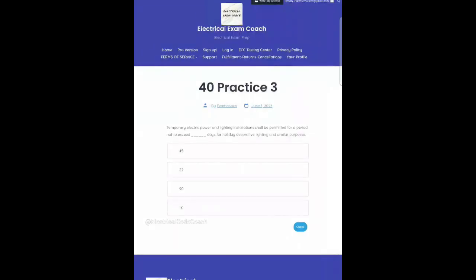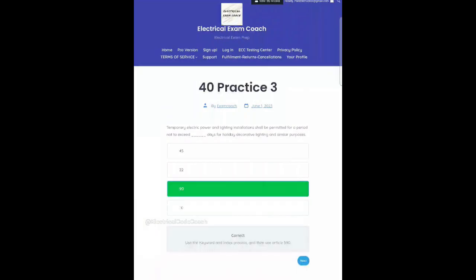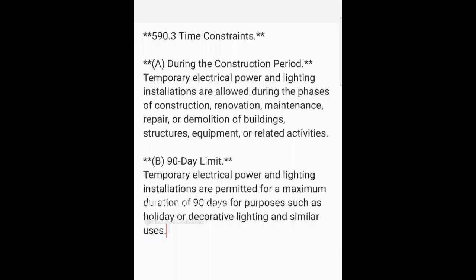Temporary electric power and lighting installations shall be permitted for a period not to exceed blank days for holiday decorative lighting and similar purposes. The correct answer is 90 days. For this one we go to Article 590. Looking at 590.3, it addresses the time constraints for temporary installations. Part A covers construction: temporary electric power and lighting are allowed during phases of construction, renovation, maintenance, repair, or demolition of buildings, structures, equipment, or related activities. Part B specifies the 90-day limit: temporary electric power and lighting installations are permitted for a maximum duration of 90 days for purposes such as holiday or decorative lighting and similar uses.